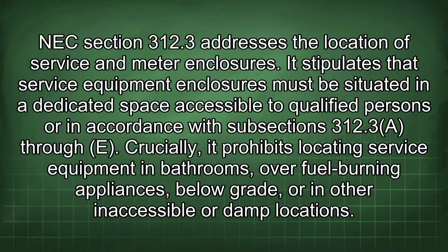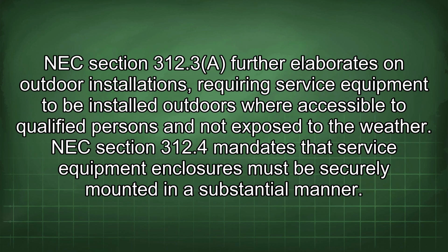NEC Section 312.3 addresses the location of service and meter enclosures. It stipulates that service equipment enclosures must be situated in a dedicated space accessible to qualified persons or in accordance with subsections 312.3(A) through (E). Crucially, it prohibits locating service equipment in bathrooms, over fuel-burning appliances, below grade, or in other inaccessible or damp locations. NEC Section 312.3(A) further elaborates on outdoor installations, requiring service equipment to be installed outdoors where accessible to qualified persons and not exposed to the weather.